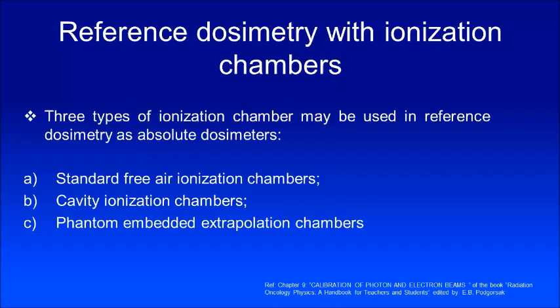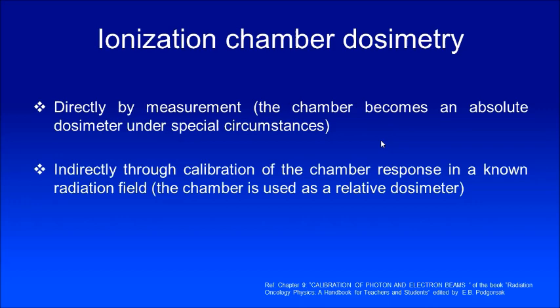But really by definition they are not, because they require a calibration factor. Can an ionization chamber be a reference dosimeter or absolute dosimeter? Yes, they can be under specific conditions: one is the standard free-air ionization chamber, cavity ionization chamber, and phantom embedded extrapolation chambers. The ionization chamber can be either an absolute dosimeter or a relative dosimeter depending on the circumstances. If you can get the dose directly by measurement, then it is absolute dosimetry. If you arrive at the dose indirectly using a calibration factor, then the ion chamber becomes a relative dosimeter.